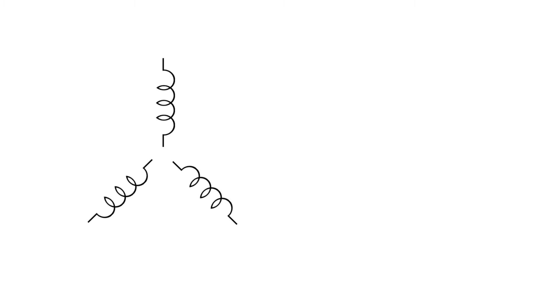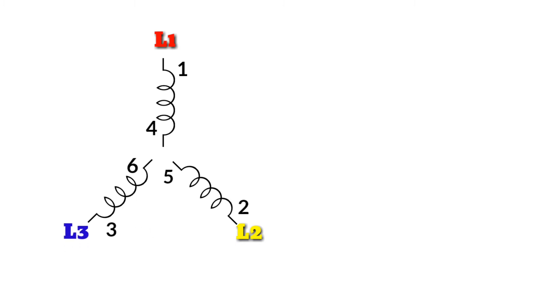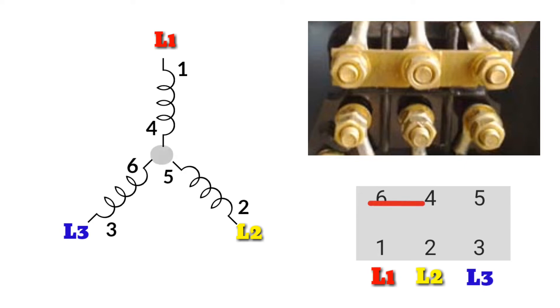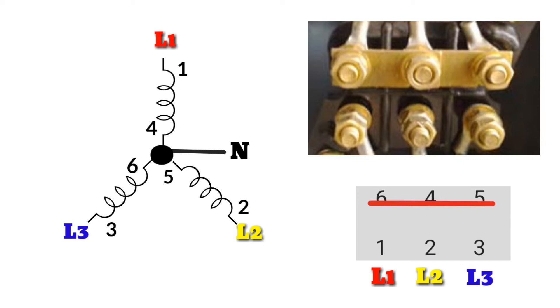This is a 6-lead star connection. Line 1 coil has number 1 and number 4, line 2 coil has number 2 and number 5, line 3 coil has number 3 and number 6. To make it a star connection, connect terminal number 6, number 4, and number 5 to each other. This point is known as the star point or neutral point N.